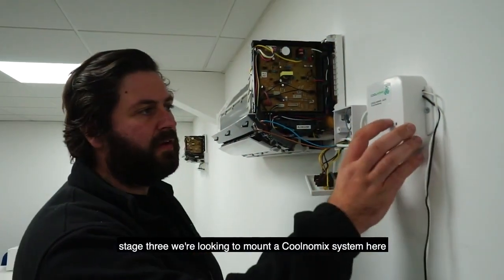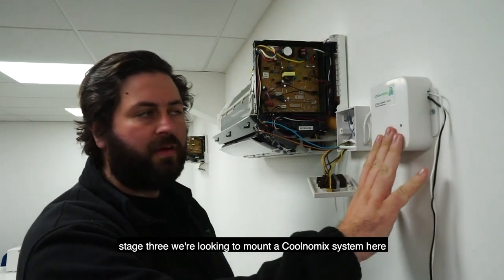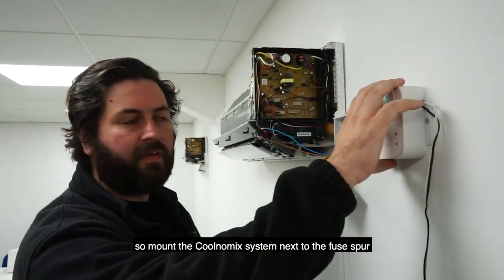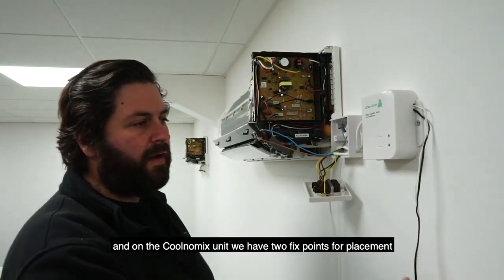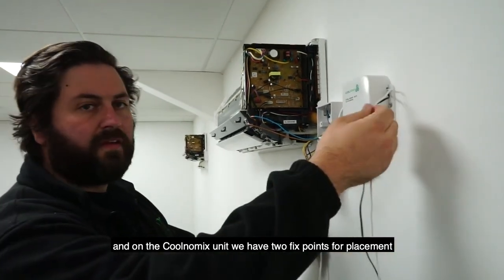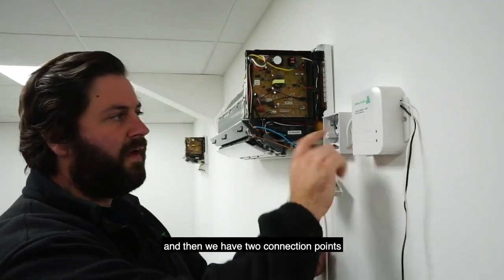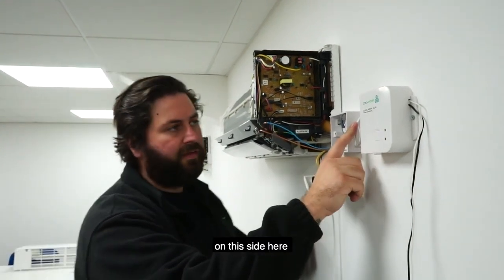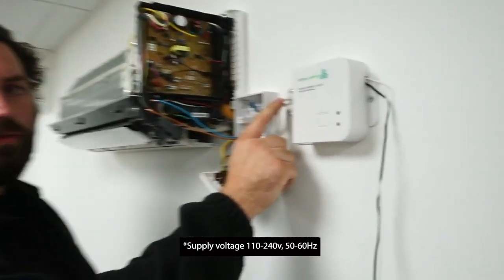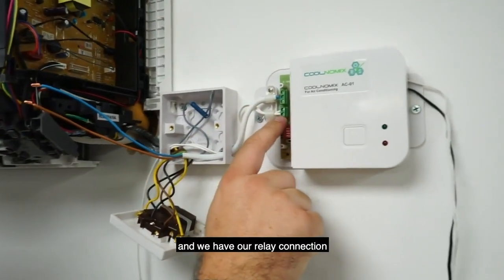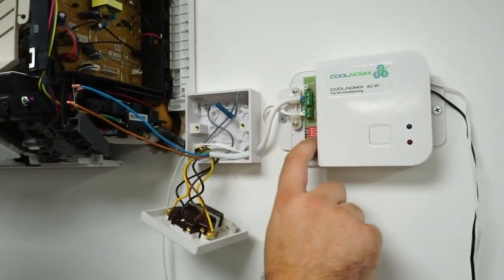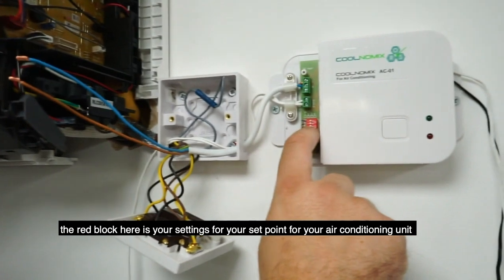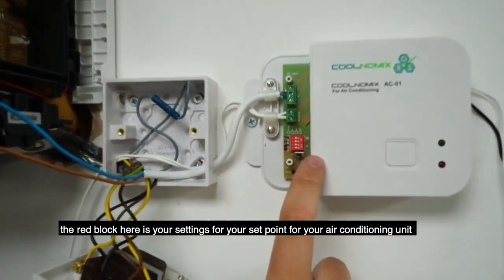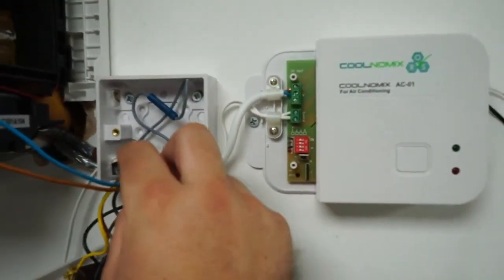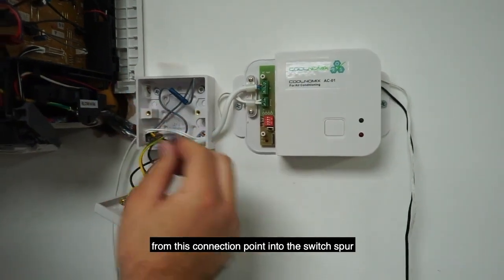Okay, stage 3, we're looking to mount the Coolnomix system here. So mount the Coolnomix system next to the fuse spur, and on the Coolnomix unit we have 2 fixed points for placement, and then we have 2 connection points. On this side here we have our 240 volt connection and we have our relay connection. The red block here is your settings for your set point for your air conditioning unit, which we'll go into after.